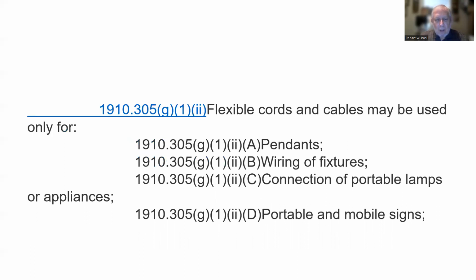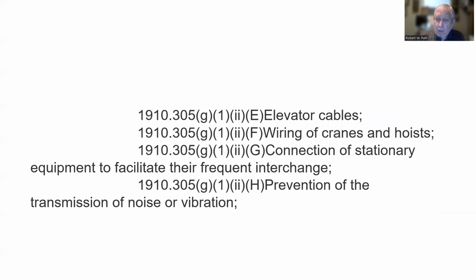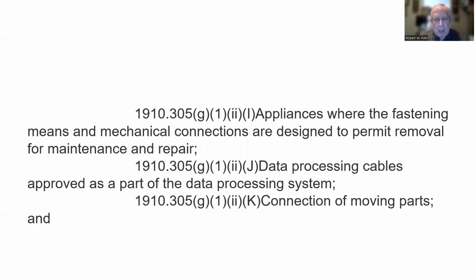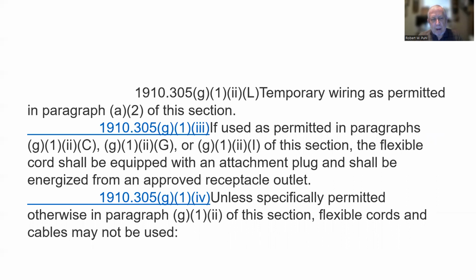Flexible cords and cables may be used only for pendants, wiring of fixtures, connection of portable lamps or appliances, portable and mobile signs. Elevator cables, makes sense. Wiring of cranes and hoists, makes sense. Connection of stationary equipment to facilitate their frequent interchange. Prevention of the transmission of noise or vibration. Appliances where the fastening means and mechanical connections are designed to permit removal for maintenance and repair. Data processing cables approved as part of the data processing system. Connection of moving parts and temporary wiring as permitted in paragraph A2 of this section. They're talking about basically extension cords, flexible cables.